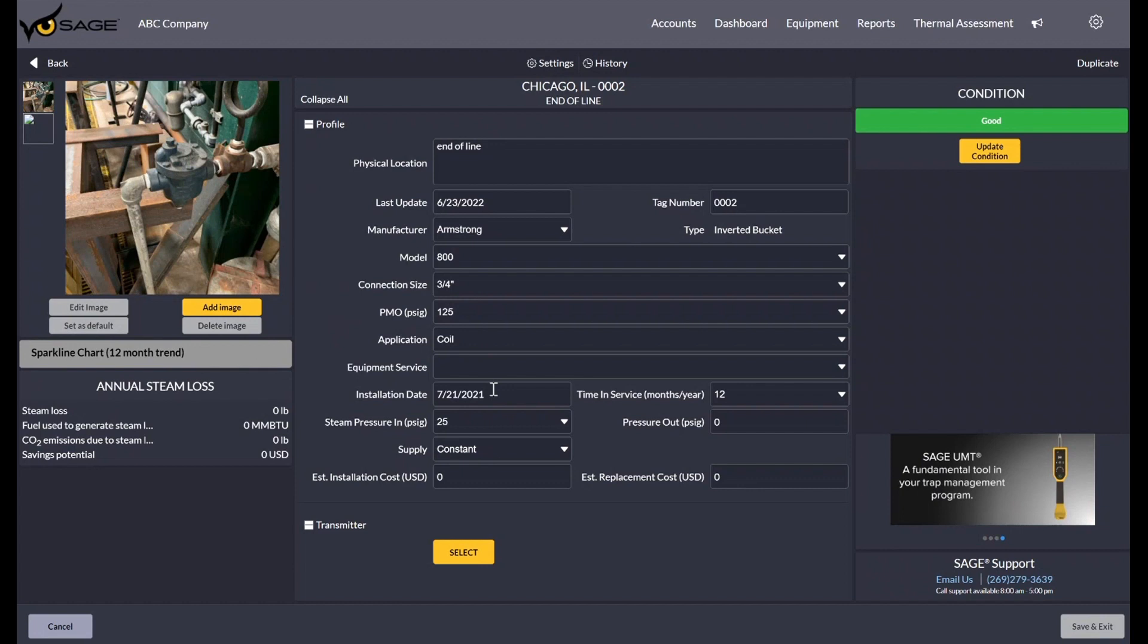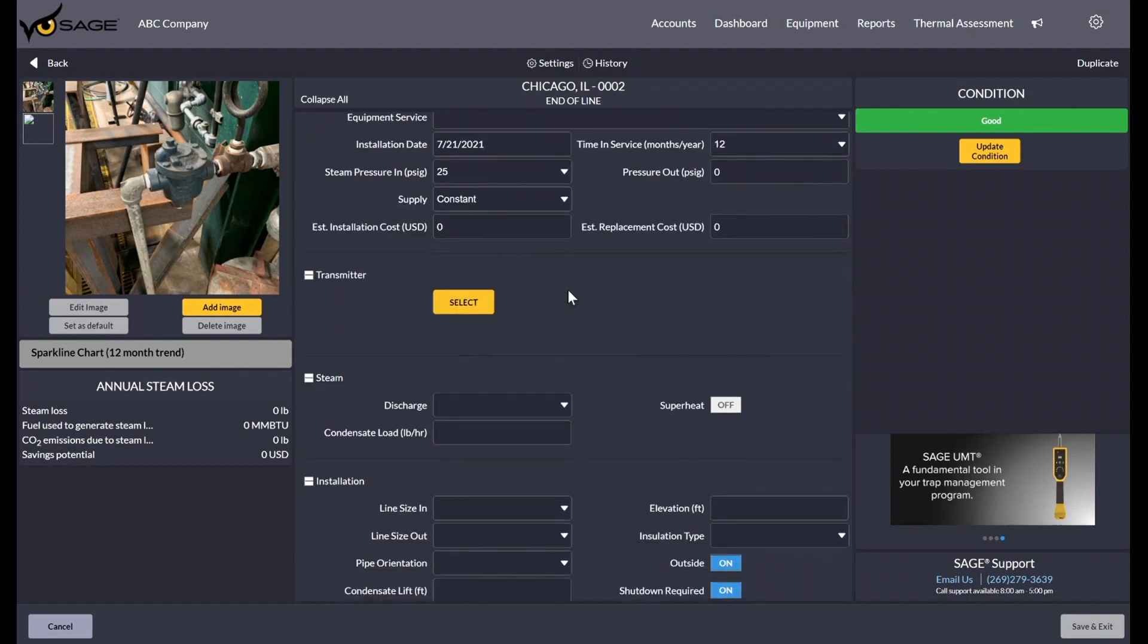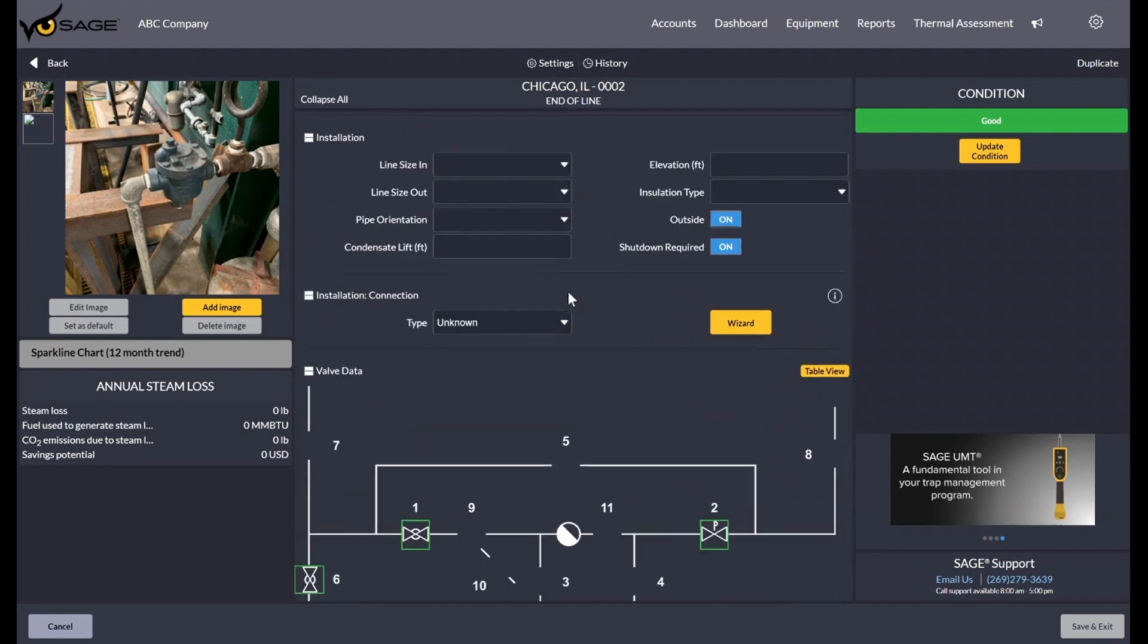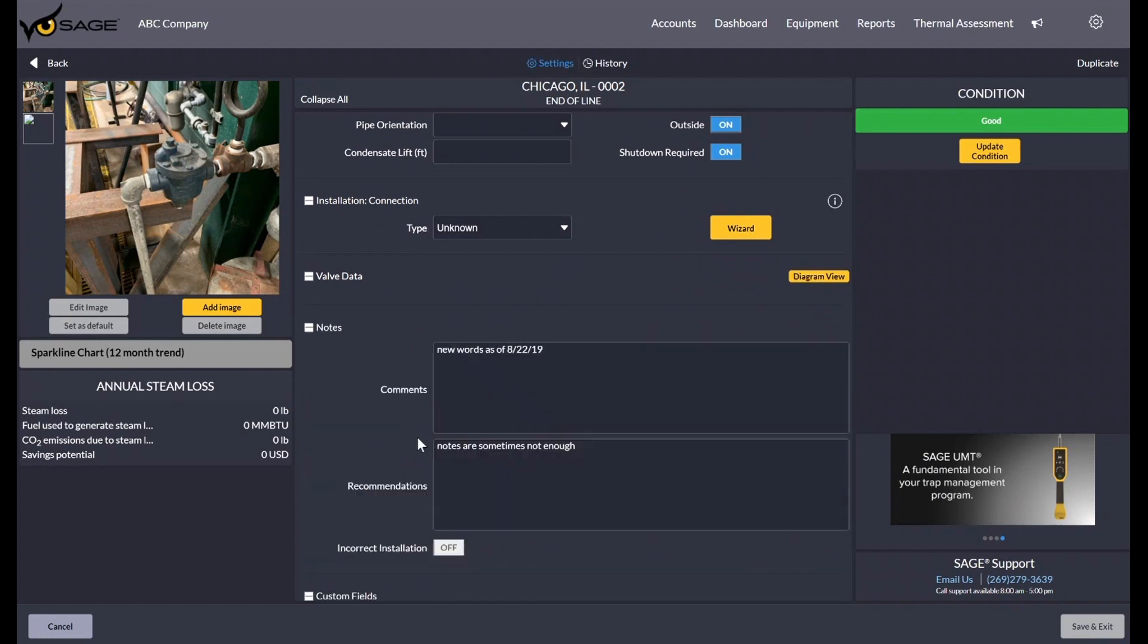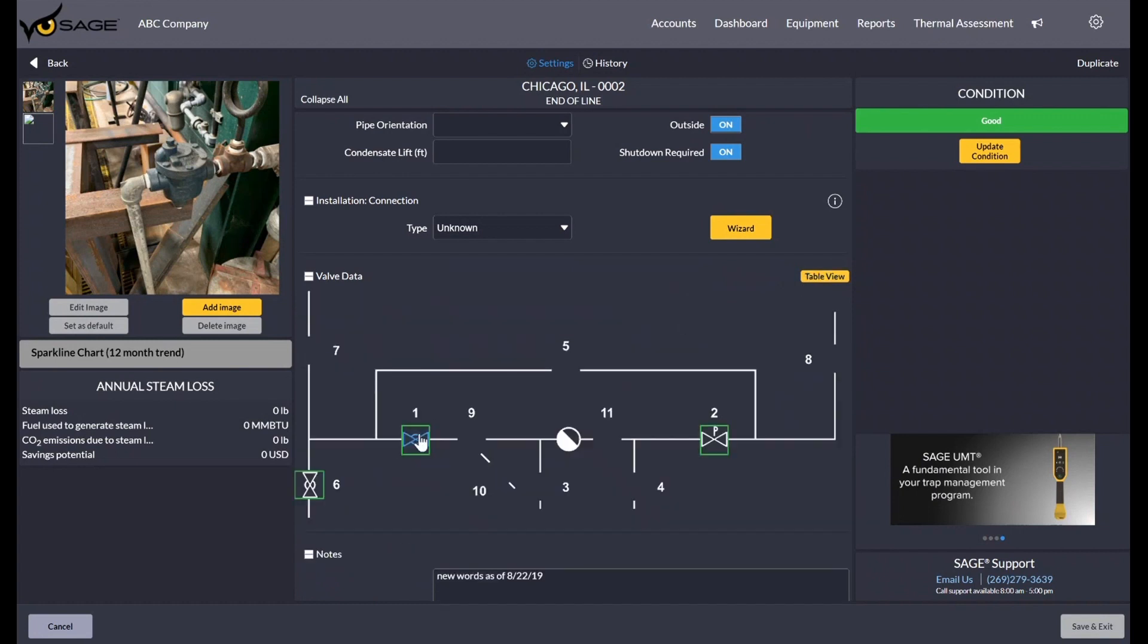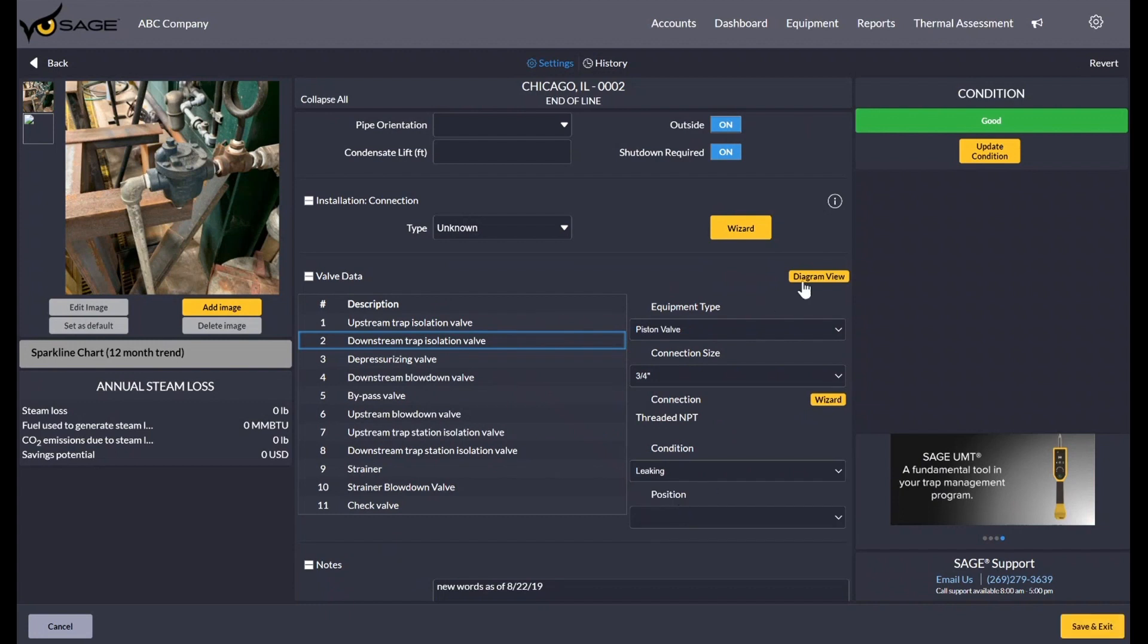You can edit all of the trap characteristics right here. If you scroll down, you'll see there's quite a bit of information you can document about each steam trap, including the valves around it in the installation. If you click on one of these, you can go ahead and fill out the information. Go back to the diagram and you can see where there is an icon, it indicates there is a valve. You can also see that the condition is kind of glanceable. If one of these valves were to be set, let's say, for example, right now, I could say this one is leaking. I go back to the diagram. It is now blue indicates that it hasn't been saved yet, but it is yellow behind it. So let me go ahead and save and exit and come back in. And if I scroll back down here, you'll see now it has a yellow box.